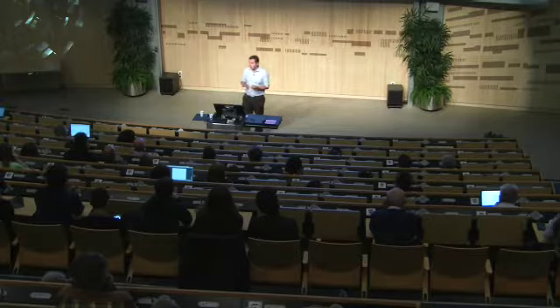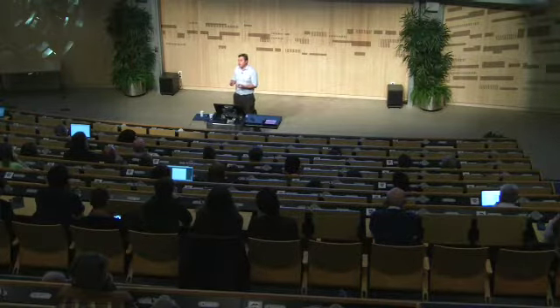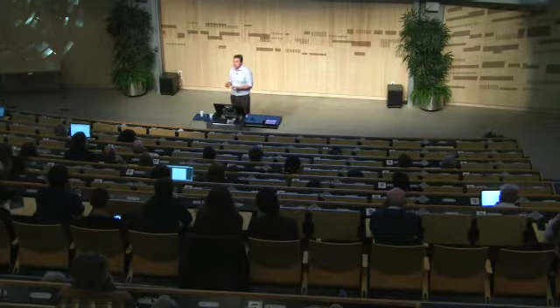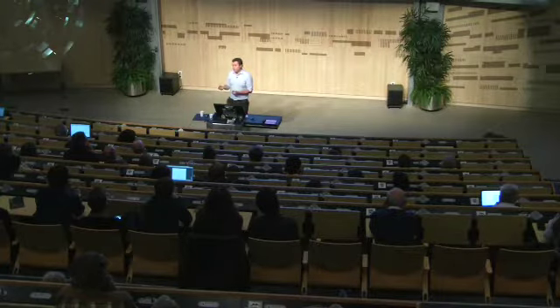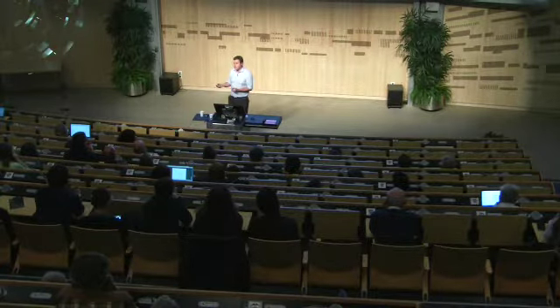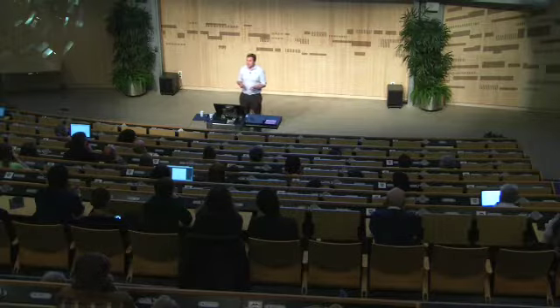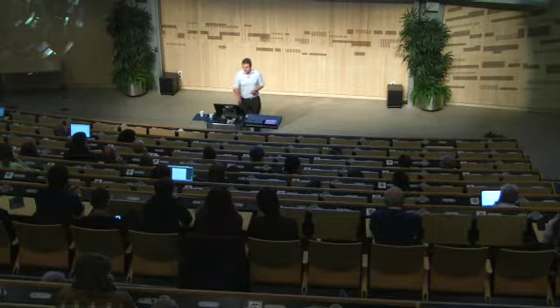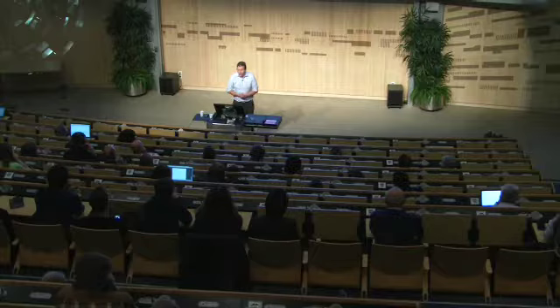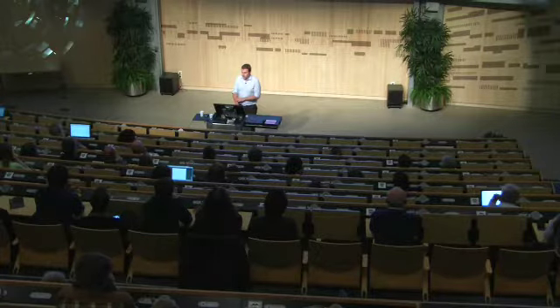So that's a little bit bad for spatial resolution, but terrible for energy resolution. So one photon of 100 keV will be counted as 2 events. One of them might be 30 and one of them might be 70. So you've immediately degraded the spectrum. So as I said, one photon of low energy can ruin the spectrum.